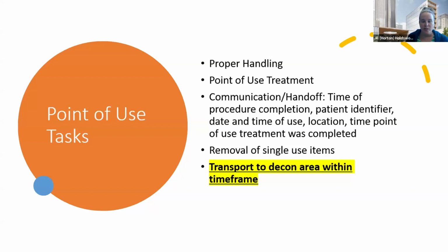These scopes can be damaged so easily. And if somebody has never been taught how to handle a scope, they're going to damage the tips of those scopes very easily. And then when they get down to the reprocessing space, they're going to fail the leak test and then have to be sent out for repair. And you're going to add up a lot of unnecessary costs. So again, proper handling, leak testing is so important, because then if it's not leak tested, it could get missed. So all of these steps become very, very important. The point of use treatment, if flushing is required, all of that becomes very important steps. Are those being followed? Is somebody actually observing to make sure that they're done correctly?